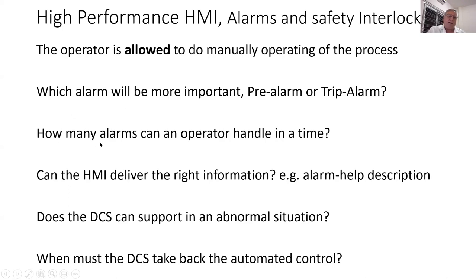Another question is, how many alarms can an operator handle, let's say in 1 hour? The normal rule of thumb is not more than 5 per hour. You need time to handle each alarm one by one and do something to avoid the shutdown. Even if you call someone in the field and he should look and fix whatever is broken, you have to have the time to avoid a trip.